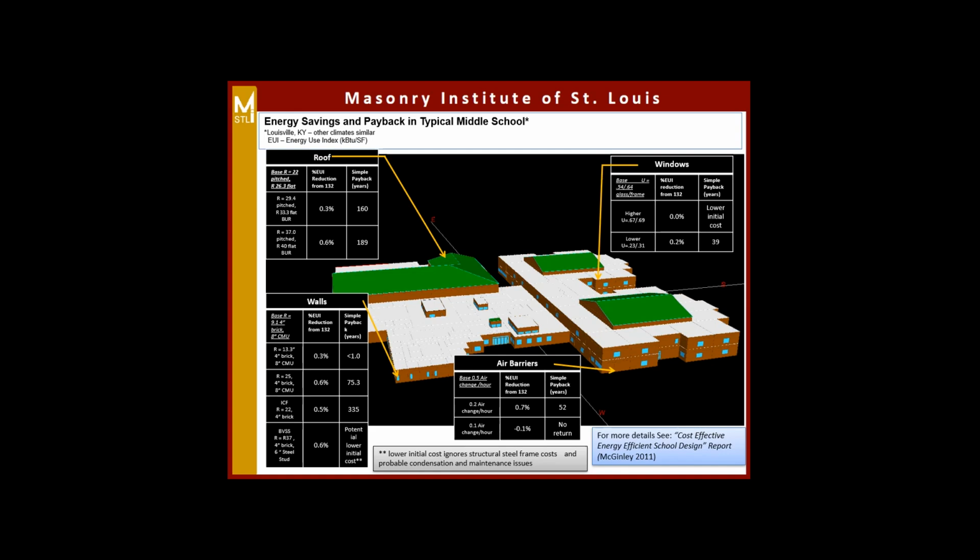Windows, here was interesting, we have U values for windows. So we backed off the U value requirements and we used a different climate zone. Climate zone 1 and 2 has higher U value allowances for those fenestrations. Lower cost and almost no impact going to crappier windows. Interesting. It's all about the amount of fenestrations. You change 10% on the fenestrations, you'll get a significant impact. Playing with the U values does almost nothing for you, right? That's another thing I wanted to bring to your attention.